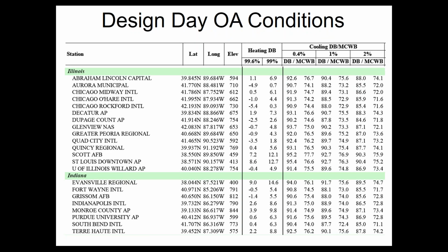Outdoor air temperatures come into play there as well. If we look at the ASHRAE handbook, if I look for Chicago, it's -1 for heating, and then either 88 or 91 for cooling, depending on which column you want to use. The code does not force you into one column or the other. In fact, it doesn't even force you to use the ASHRAE handbook tables. You can use other weather data sources if you want, but you have to cite some cognizant weather source.